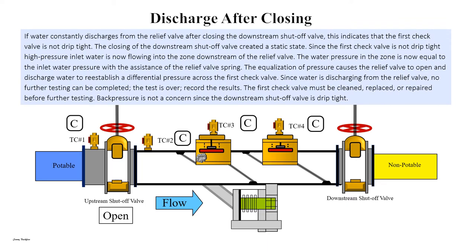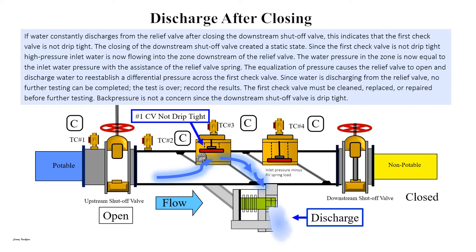Discharge after closing. If water constantly discharges from the relief valve after closing the downstream shutoff valve, this indicates that the first check valve is not drip tight. The closing of the downstream shutoff valve created a static state. Since the first check valve is not drip tight, high pressure inlet water is now flowing into the zone downstream of the relief valve. The water pressure in the zone is now equal to the inlet water pressure with the assistance of the relief valve spring. The equalization of pressure causes the relief valve to open and discharge water to re-establish a differential pressure across the first check valve. Since water is discharging from the relief valve, no further testing can be completed. The test is over.